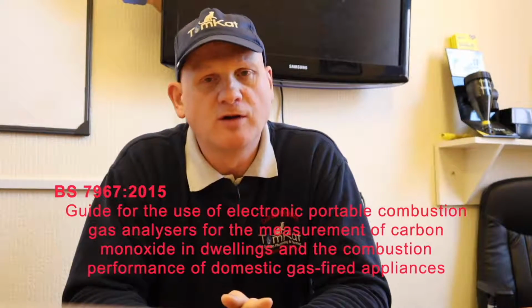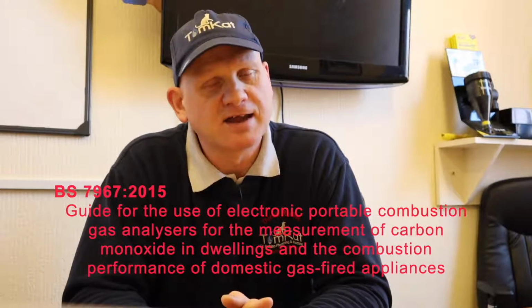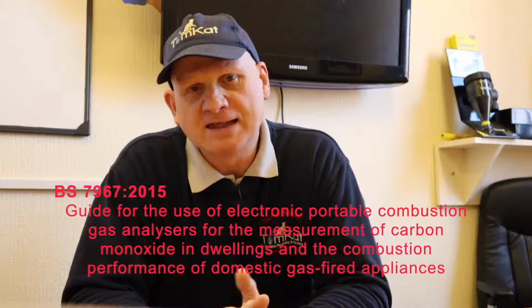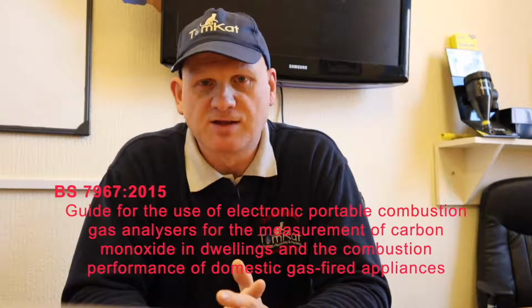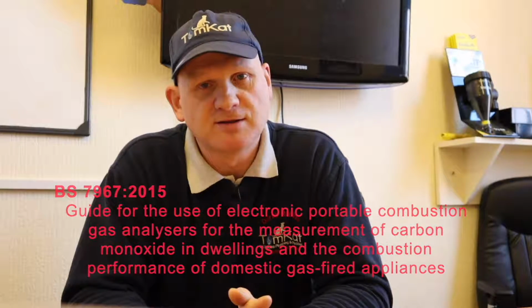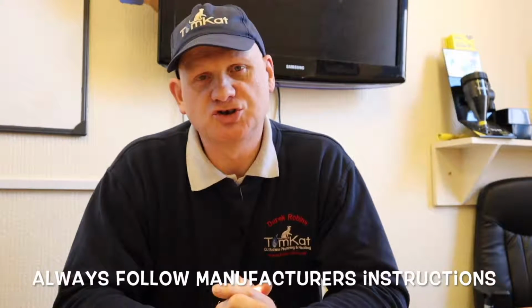It's also very vital and important that the gas engineer has their flue gas analyzer calibrated every 12 months, even if they've hardly used the analyzer within that 12 months, because the cells within the unit will need to be checked and replaced. When using the flue gas analyzer on boilers, the engineer must understand that when they are sampling the products of combustion from this boiler, there is a lot of water vapor within there, so the byproducts of burning natural gas are carbon dioxide and water vapor. So to protect these flue gas analyzers, the manufacturers use a bowl. In this bowl, there will be a filter and a water catcher, and the engineer must understand when and where they must replace this filter and clean the trap out of the moisture.